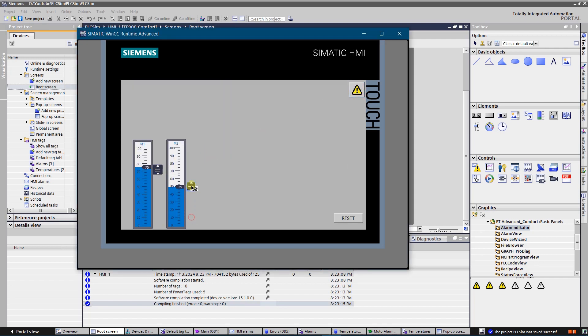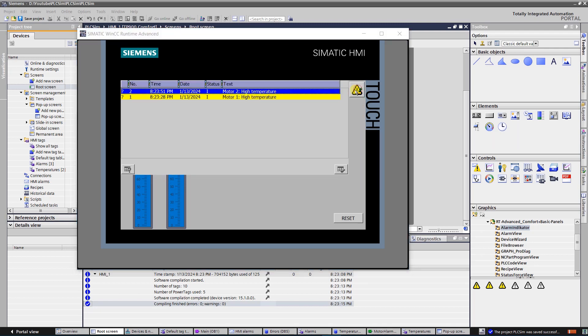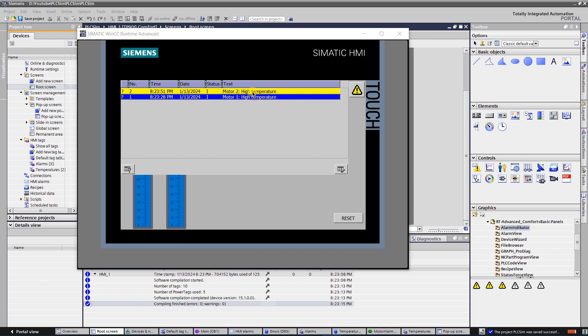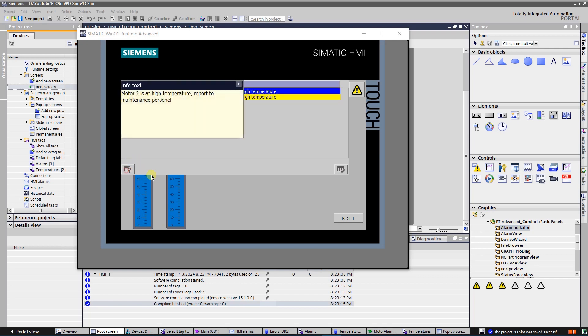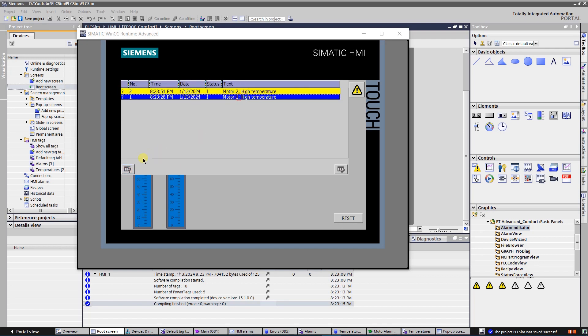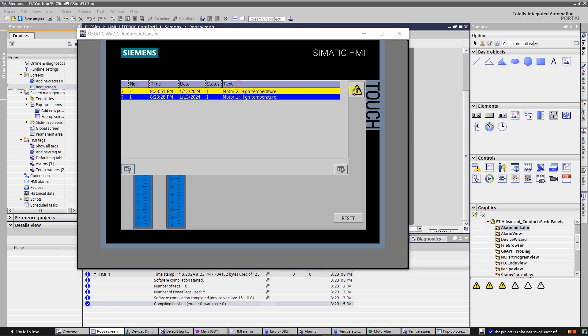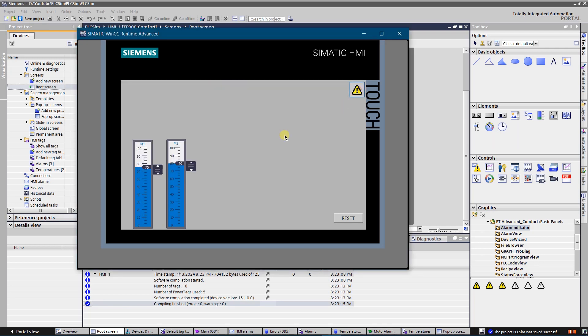Let's try to generate alarm for motor 2. There are two alarms now, both of the type of warning. Let's look for the info text. The operator has got clear directives on both warnings.